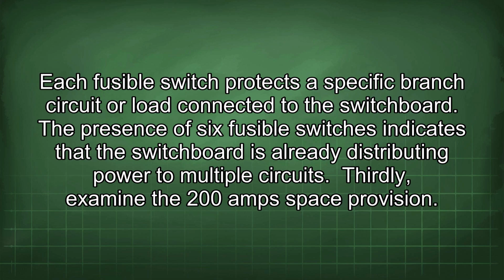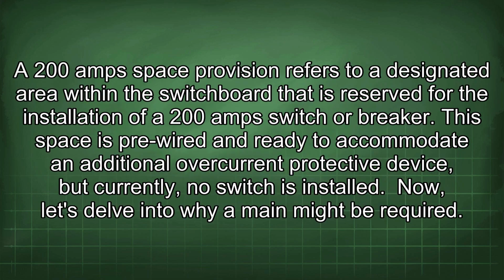Thirdly, examine the 200 amp space provision. A 200 amp space provision refers to a designated area within the switchboard that is reserved for the installation of a 200 amp switch or breaker. This space is pre-wired and ready to accommodate an additional overcurrent protective device, but currently, no switch is installed. Now let's delve into why a main might be required.